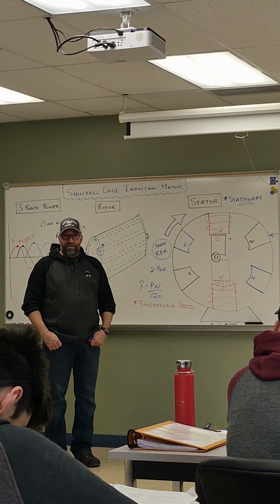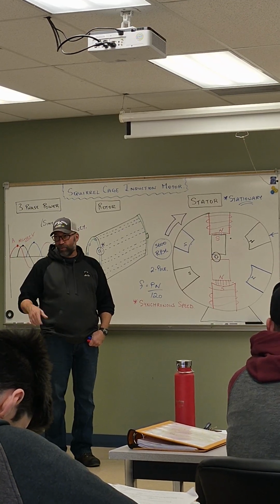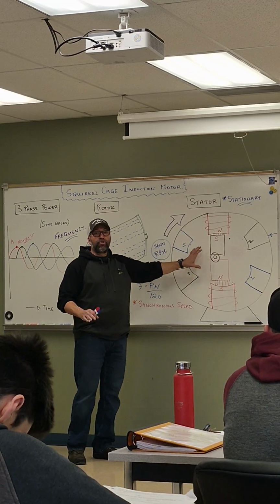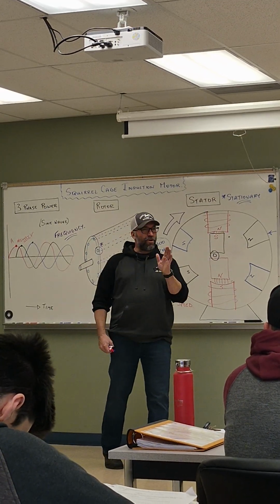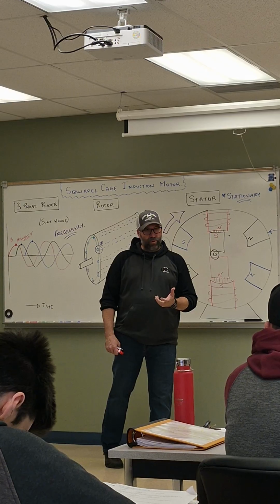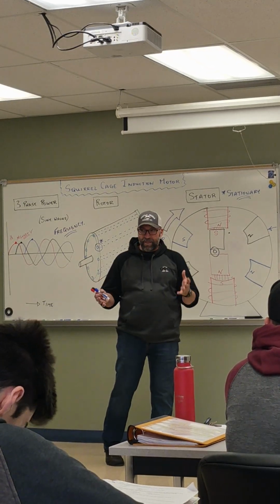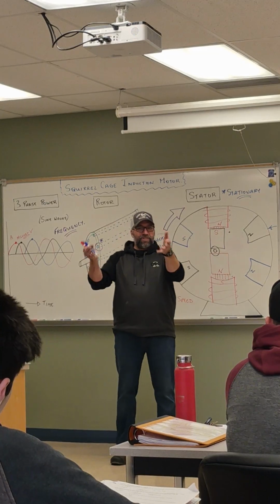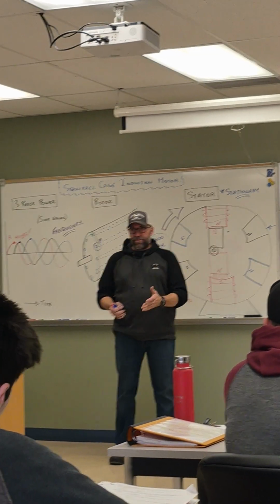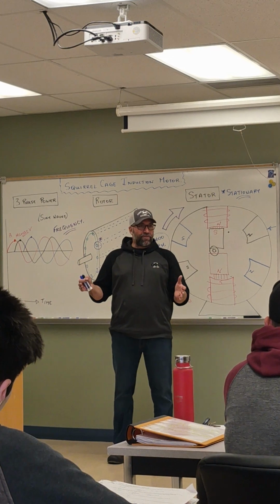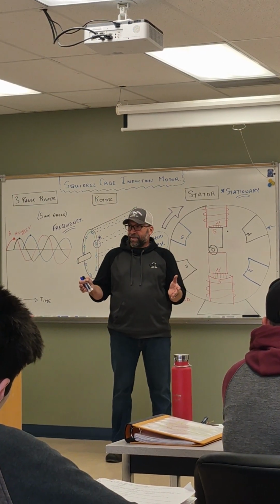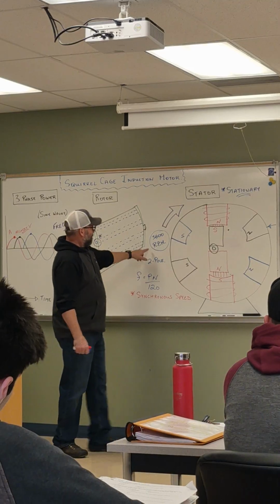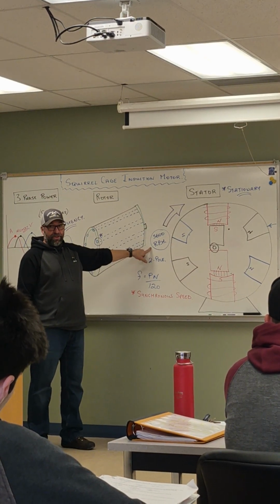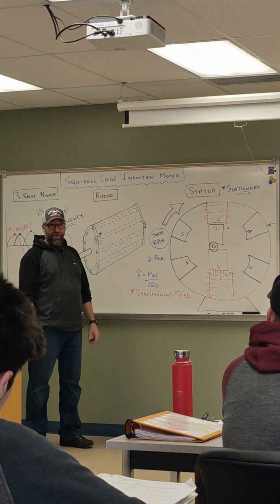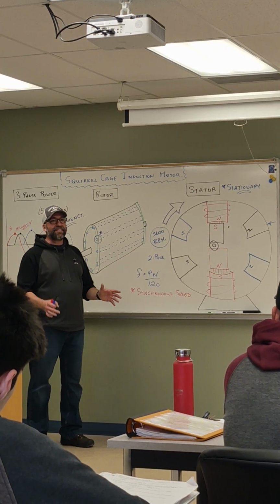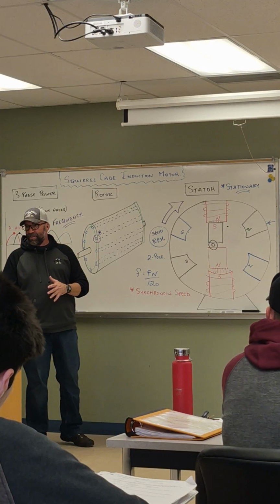And so we love these things in the electrical world for a couple of reasons. Number one, with a synchronous motor driven from a variable frequency drive, you know exactly how fast it's going. The squirrel cage motor doesn't do that. You have a VFD that's changing the speed. You can run a motor at 30 hertz instead of 60, and you can say it's going half as fast at 30 as it is at 60, but the slip increased on a squirrel cage, so you don't really know how fast it's going. With a synchronous motor, 60 hertz, 3600 RPM, run it at 30 hertz, it's exactly half of that. Run it at 1/3 of the hertz, it's exactly 1/3 of that.